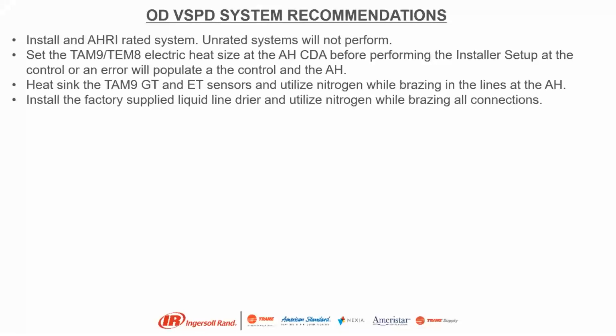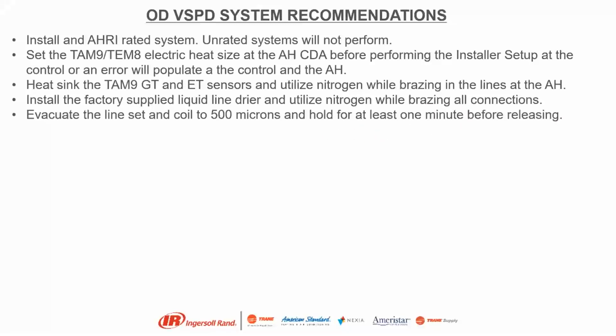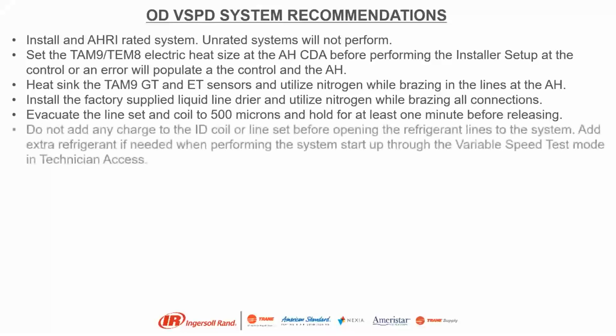Install the factory supplied liquid line dryer and utilize nitrogen when brazing. I didn't touch too much on it in this one, but nitrogen's a must. If you're not using nitrogen while brazing, you have to. Evacuate the line set and coil to 500 microns and hold for at least 1 minute before releasing. You got to do a good vacuum. Do not add any charge to the indoor coil or line set before opening refrigerant lines.